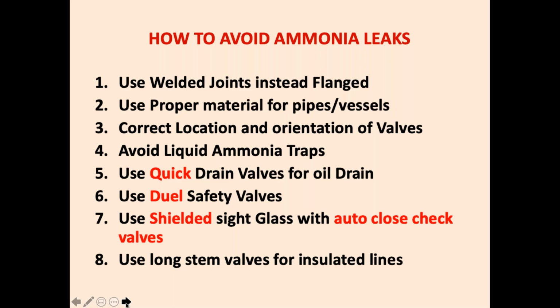Use dual safety valves. So if one valve is operated, you don't have to stop the plant. You can use a dual safety valve, so the second safety valve can come into operation. To avoid leaks from the sight glass, use auto-closing valves at the inlet and outlet and a shielded sight glass, so that even if it breaks, the auto-closing valves will close the ammonia supply to the sight glass and not much danger will take place.